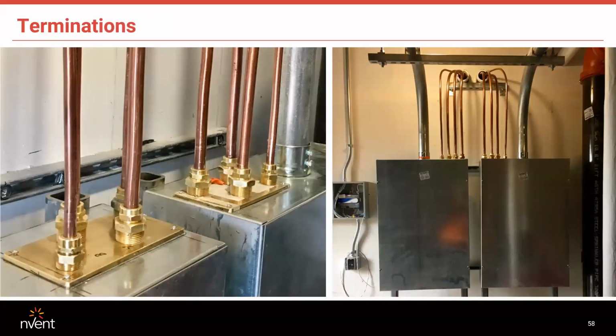Interesting slide here. Note those brass entry plates that the cable is passing through. As per the NEC, when you have individual conductors penetrating a ferrous enclosure, there is the potential for induction heating to take place. So in order to prevent any induction heating when you're using our single conductor cables, we require a brass entry plate, which we supply, that the cables pass through.